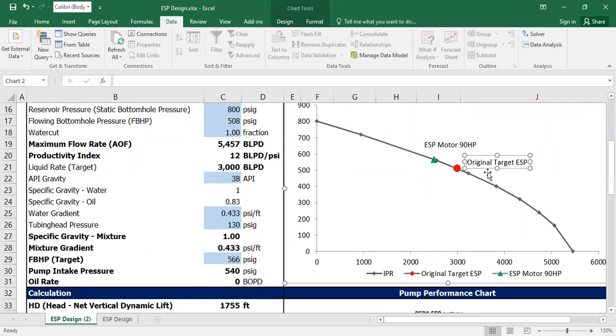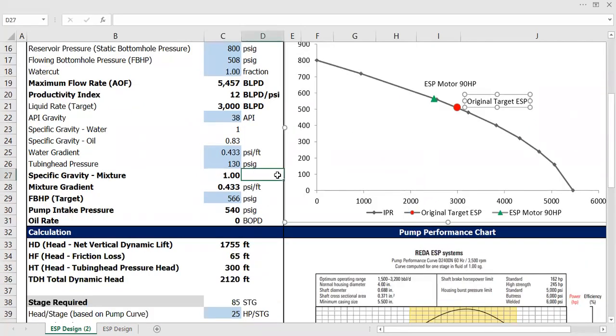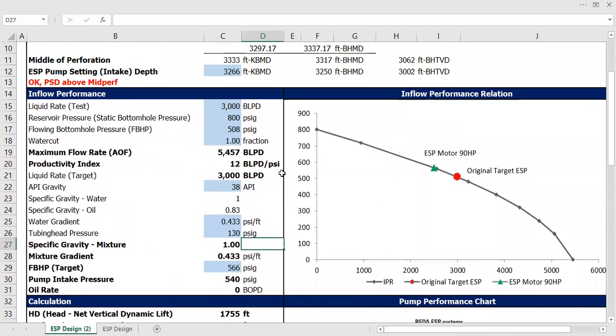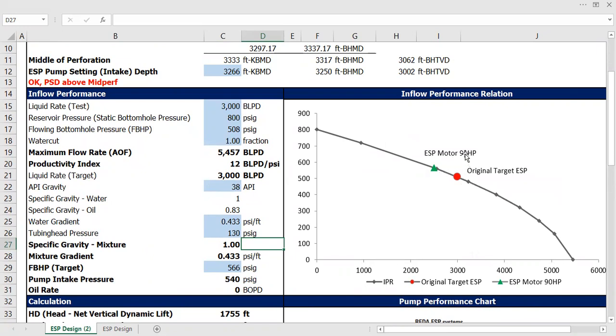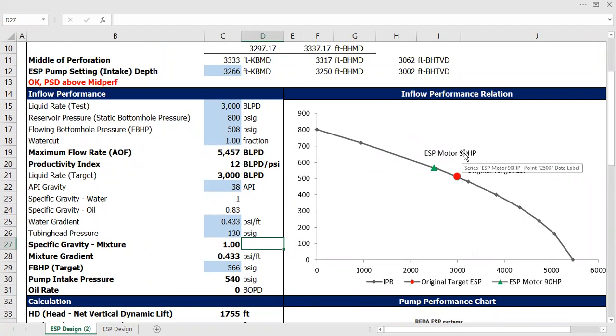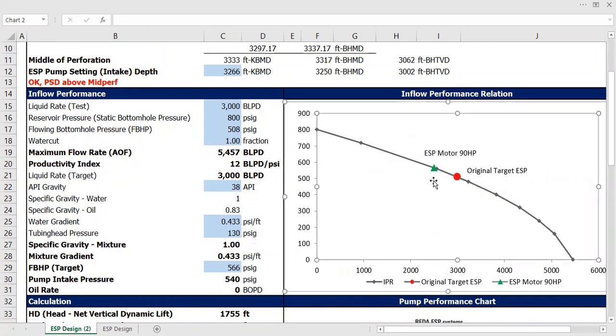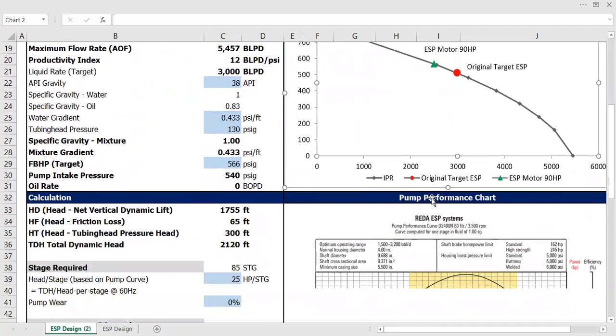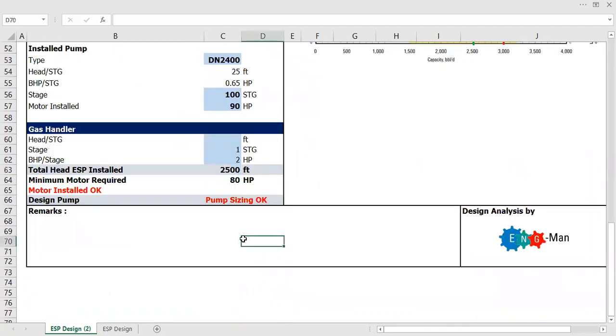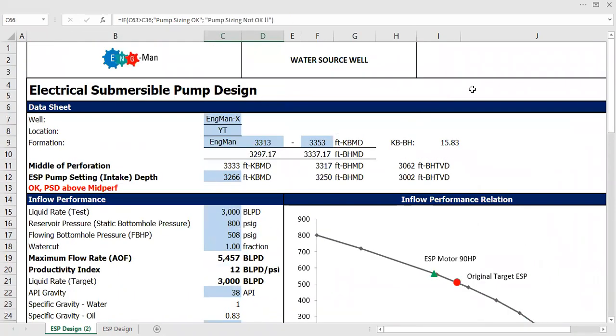If you have everything good, big motor available, you can target 3000. But considering that you only have motor of 90 horsepower, you need to lower down your target. In this case I lower down my target from 3000 to 2500 so that I can go with the execution, but with the restriction that I have, which is restriction in motor availability. I only have motor of 90 horsepower, so I lower down my target to 2500 barrel liquid per day for my water source.